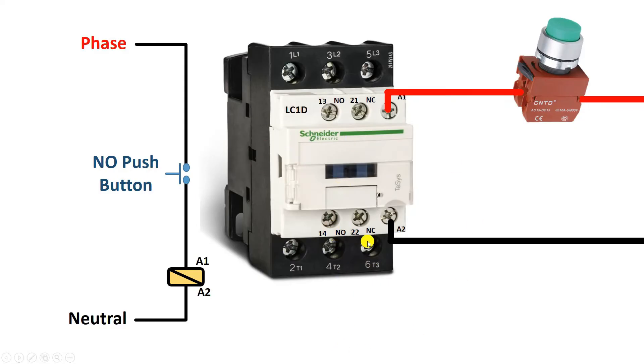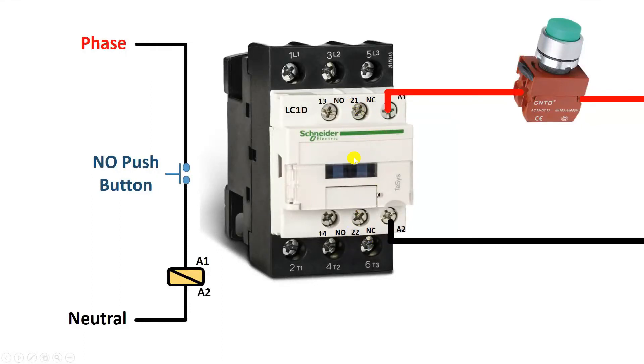Besides the power terminals, the NO and NC contacts of the contactor also change. Above the contactor, NO is written here, meaning when the contactor is off, power supply at terminal 13 won't reach terminal 14. Power supply connected at terminal 13 will come to terminal 14 only when the contactor is turned on. Terminals 21 and 22 are of NC contact. Power supply of the NC contact will always flow forward — even when the contactor is off, power supply at this point will still flow through. But when the contactor turns on, this NC contact will open, the circuit will break, and power supply connected at this point will not reach the other point.